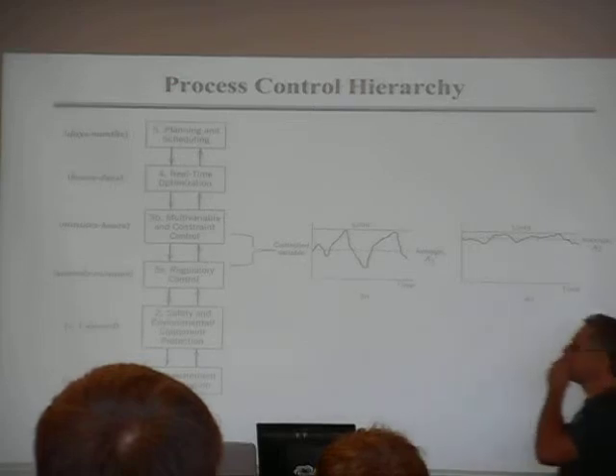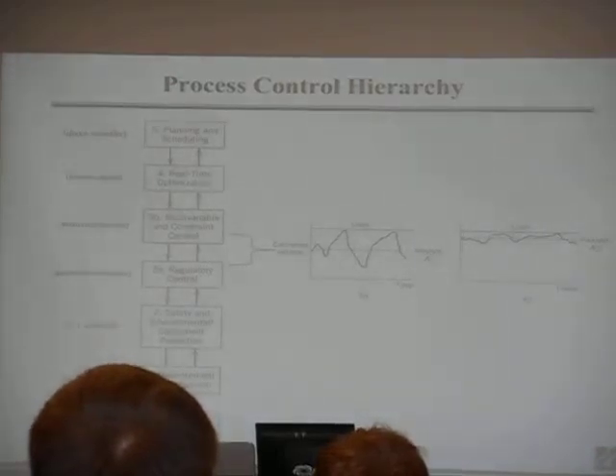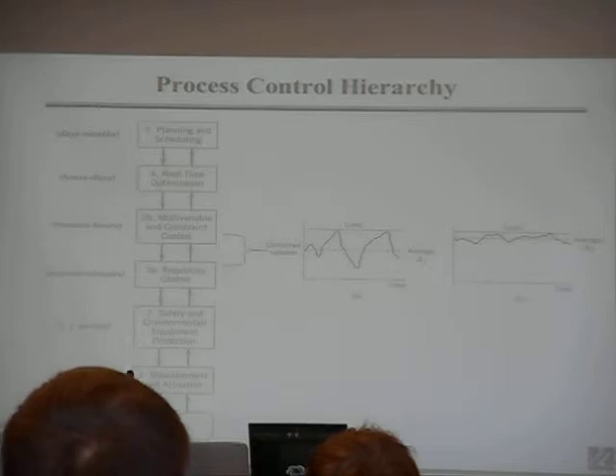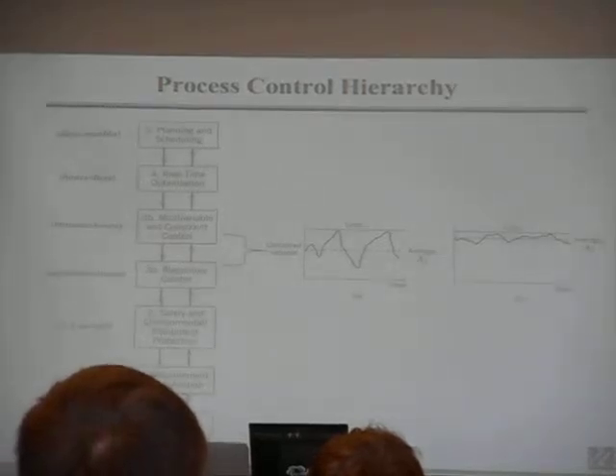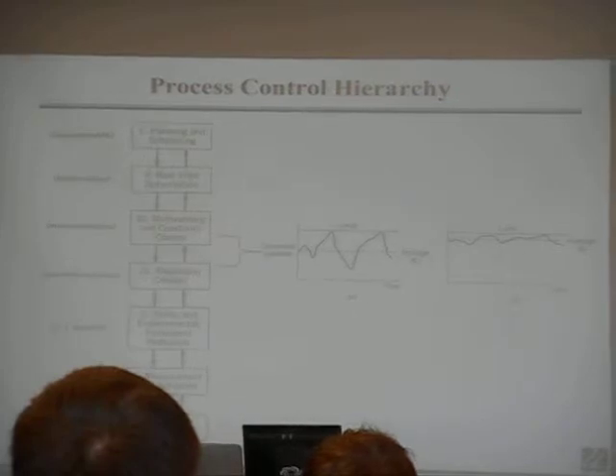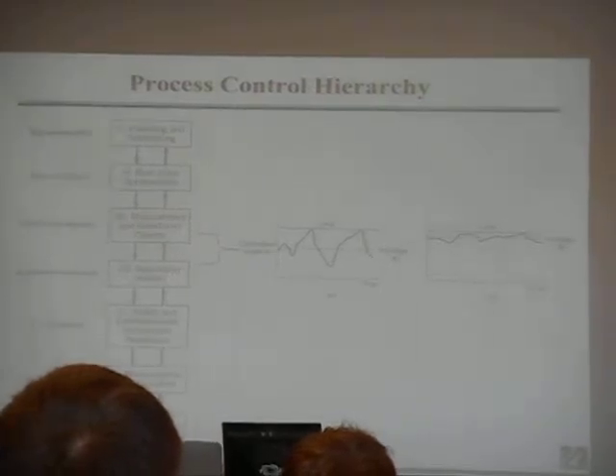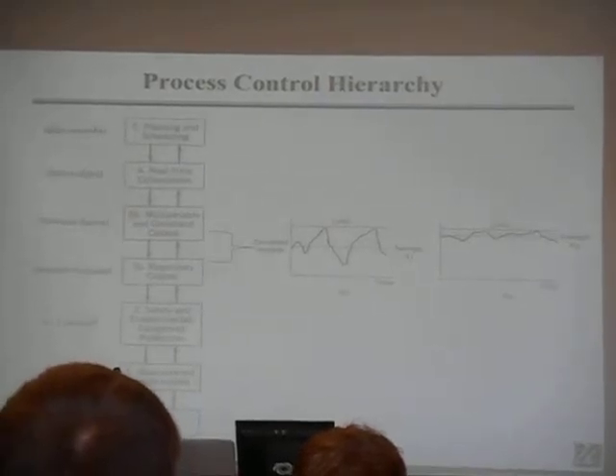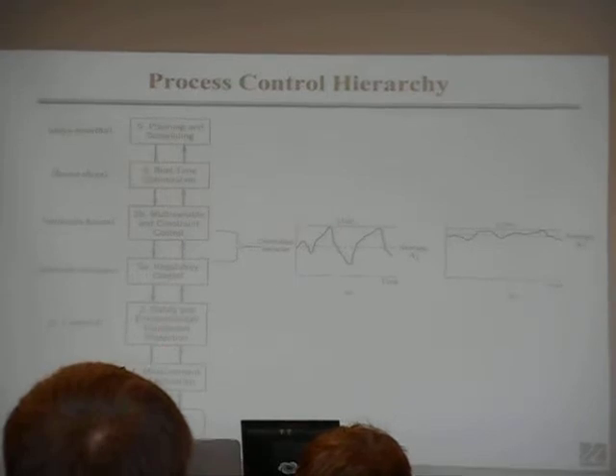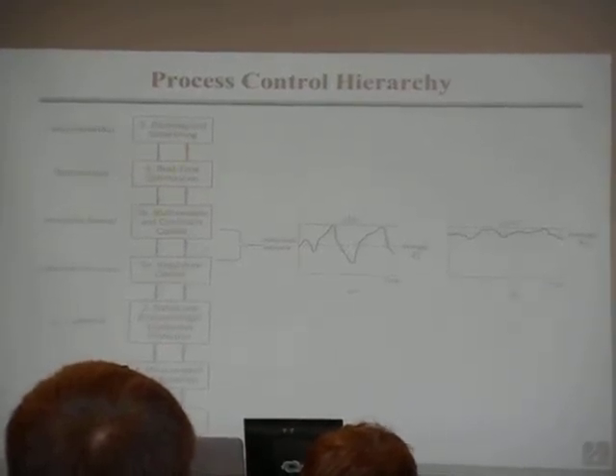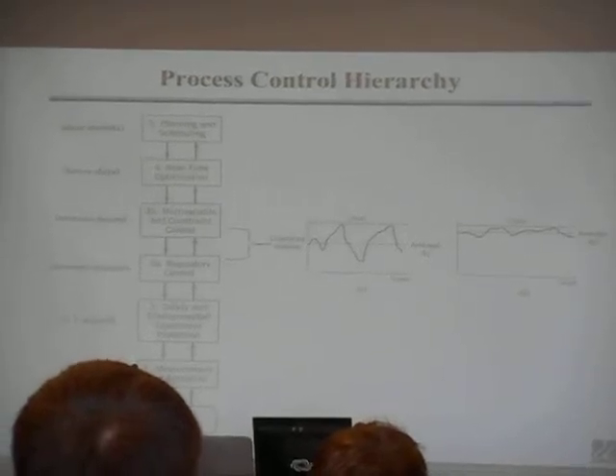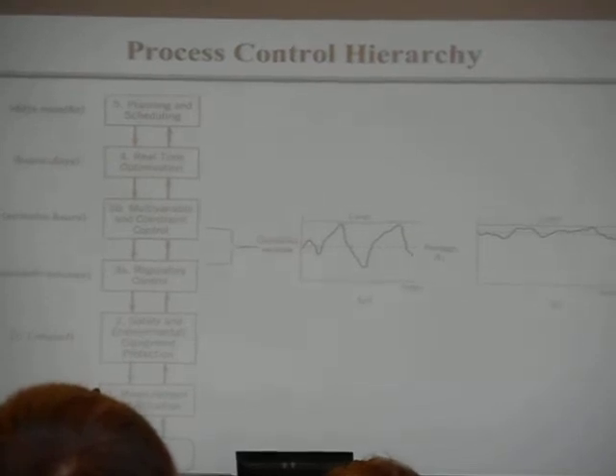If you look at a typical plant, these are all the layers of control meant to avoid what we just saw. First you have the process, then you have measurement and actuation — measuring flow, temperature, pressure, and typically moving valves — on a time scale of less than a second. Then you have interlocks and safety systems put in place to make sure what you just saw does not happen. There's a control system that overrides the main control system and just shuts everything down.